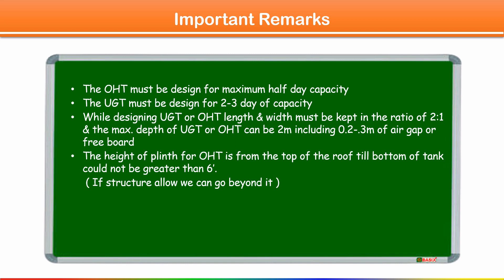Regarding the height of the plinth for OHT: since we generally place the overhead tank above the terrace, the height from the top of the roof to the bottom of the tank should not be greater than 6 feet. If you want to go beyond that, you need approval from a structural engineer. Also, overhead tank filling time can be taken as 1 to 3 hours for a small tank.